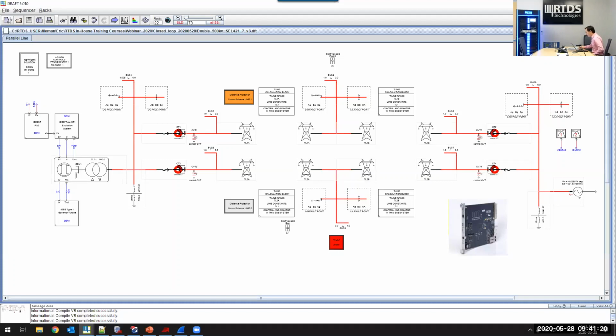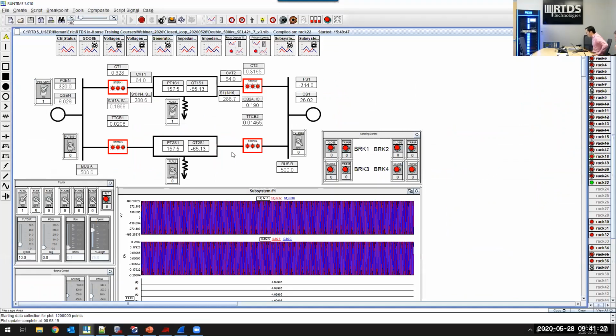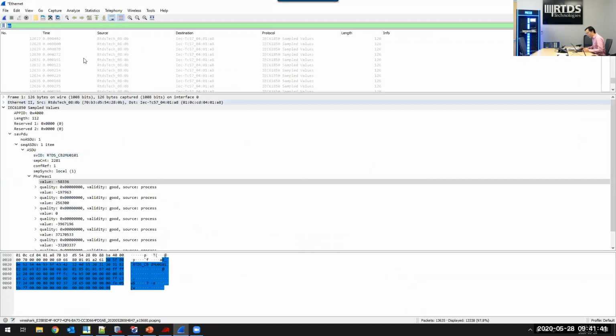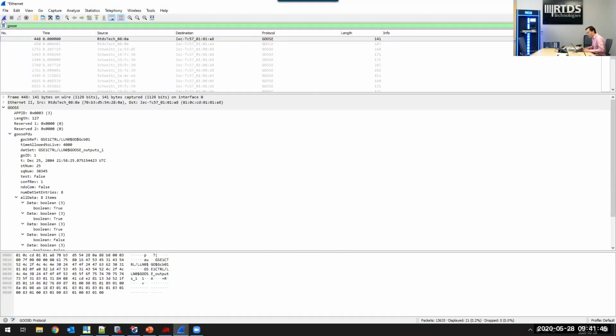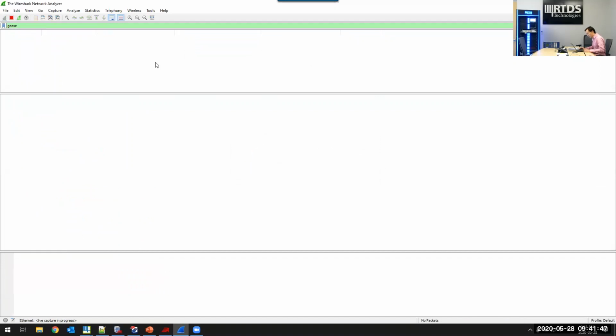So let's move on to the runtime. Once the simulation is started, you may verify the Goose and the sample value messages that are sent out from either GTNet or the relay in Wireshark. For example, I have Wireshark open here. I can just type in a filter, Goose, and then do a quick capture.